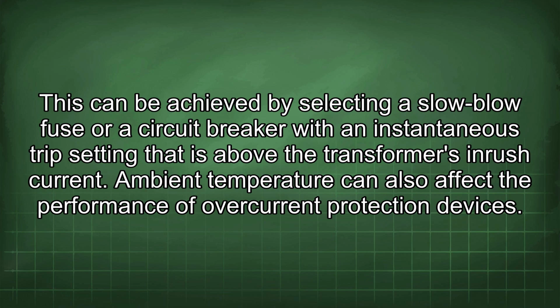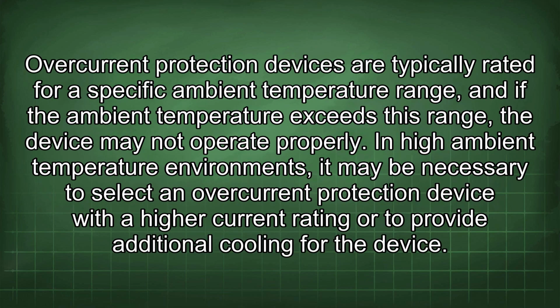Ambient temperature can also affect the performance of overcurrent protection devices. Overcurrent protection devices are typically rated for a specific ambient temperature range, and if the ambient temperature exceeds this range, the device may not operate properly. In high ambient temperature environments, it may be necessary to select an overcurrent protection device with a higher current rating or to provide additional cooling for the device.